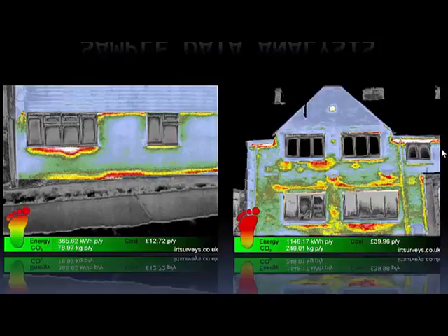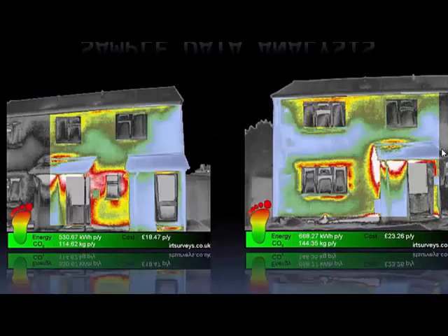Here you've got typical slumped insulation. We can see at the top of these windows this pattern where you can see the slump. This is where the insulation has either over time coagulated and fallen via gravity down to the bottom, or again it could be that moisture has gotten in at the top of the cavity and has soaked that down.